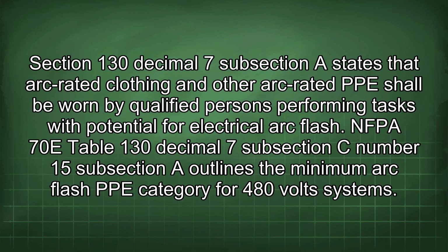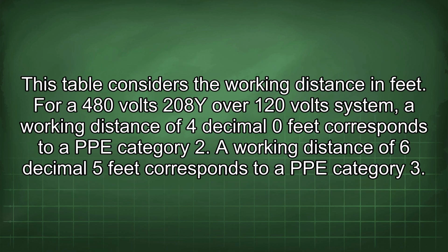Section 130.7 states that arc-rated clothing and other arc-rated PPE shall be worn by qualified persons performing tasks with potential for electrical arc flash. NFPA 70E Table 130.7 subsection C number 15 outlines the minimum arc flash PPE category for 480 volt systems. This table considers the working distance in feet.